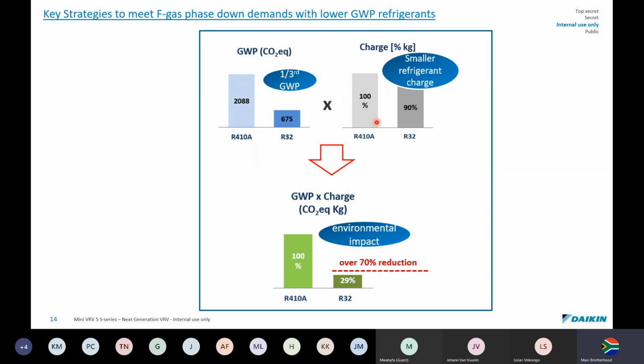And also when you look at the charge, R32 uses 10% less refrigerant charge. So when you combine the global warming potential as well as the charge that you've got to add into these systems, you generally see that the overall environmental impact, if there's a leak, we're using less gas and the gas is less harmful, there's a 70% reduction in what it can do to the environment. So it's only 29% damage to the environment compared to R410A doing 100% damage. So it's pretty much a no-brainer for Daikin to have gone to select R32 refrigerant because of the environmental impact.